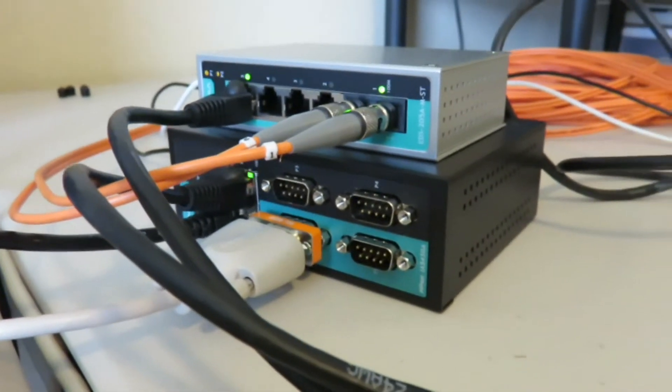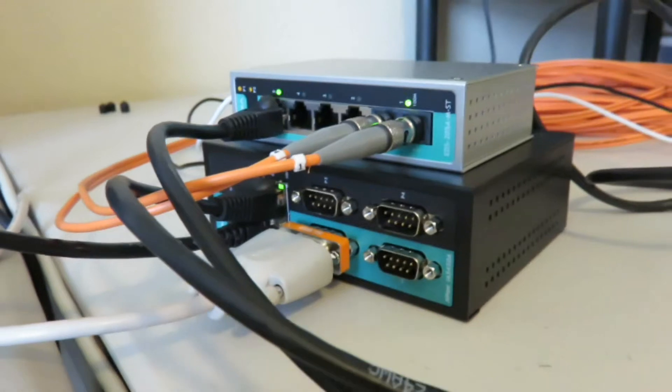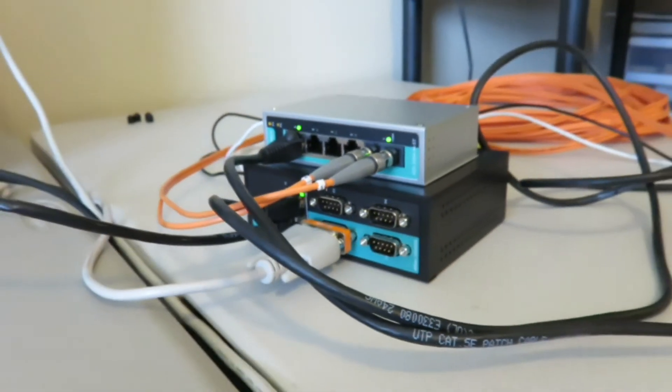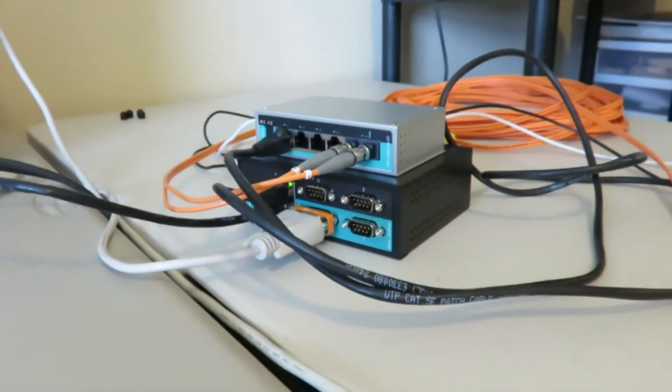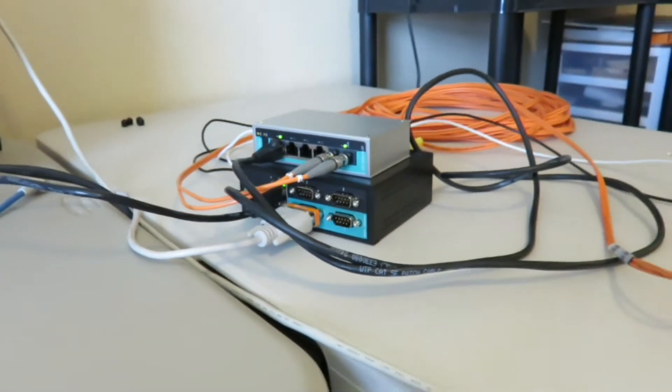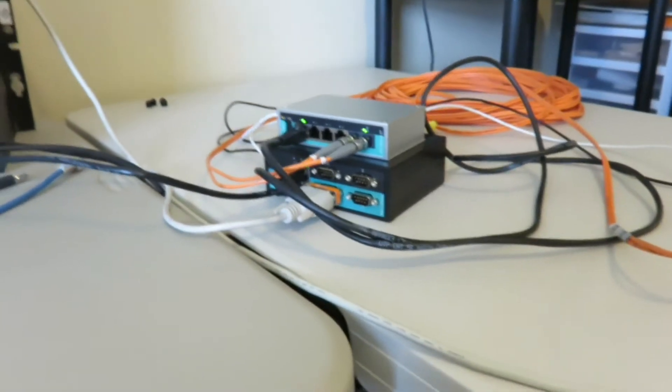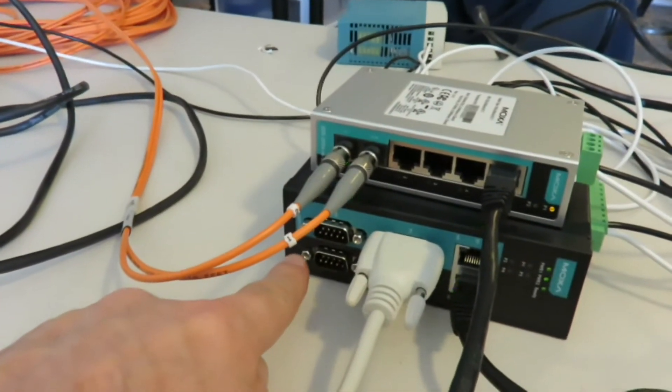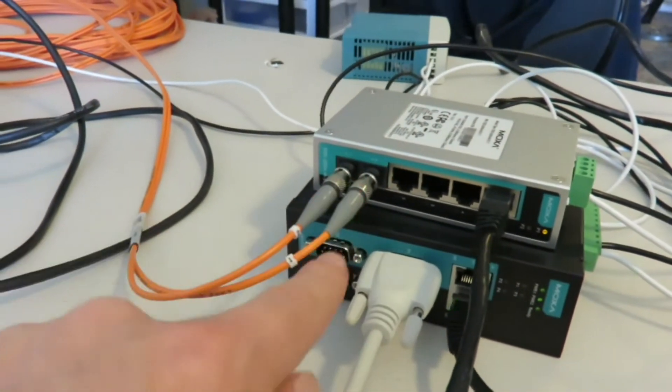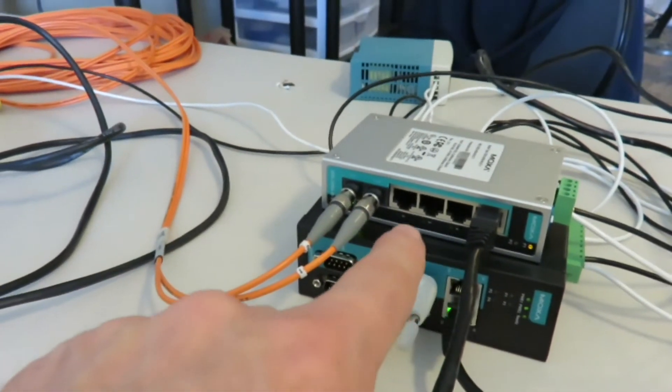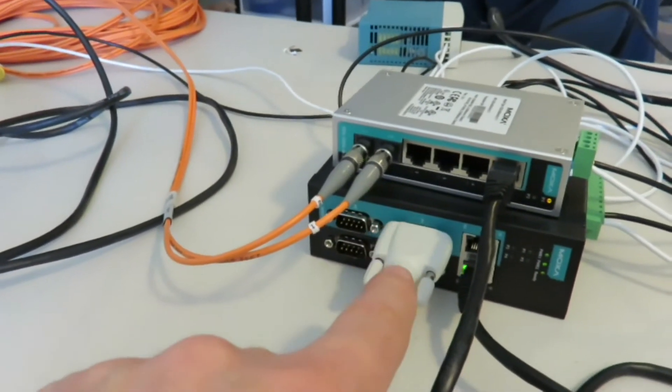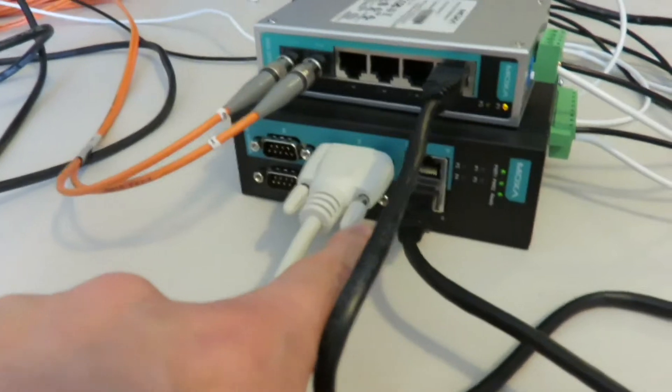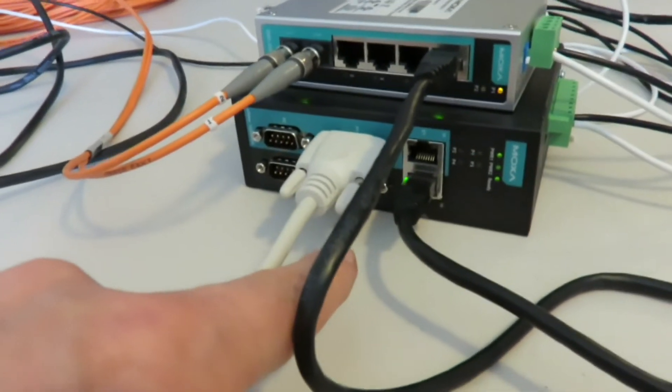When you're putting these MOXAs together in this configuration, again this is pair connection mode where we have a slave and a master. The slave and the master being the MOXA device not the switch. The switch, you don't have to do any configuration on the switch at all. Only on the bottom device here which is the NPort.